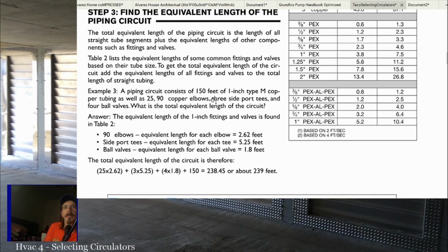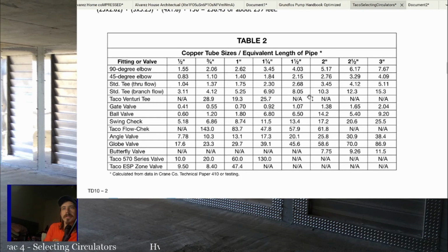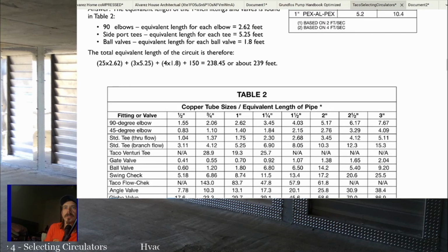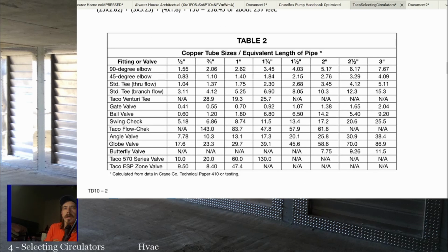So, example 3: a piping circuit consists of 150 feet of 1-inch M copper tubing, as well as 25 90-degree elbows, 3 side port T's, and 4 ball valves. What is the total equivalent length of the piping circuit? The equivalent length of the 1-inch fittings and valves is found in table 2. So here's the table they're talking about. And you can see for 1/2-inch pipe, we have equivalent lengths for everything. 3/4, same thing. 1-inch, same thing. So before we finish this example, I want to point a couple things out in this table.